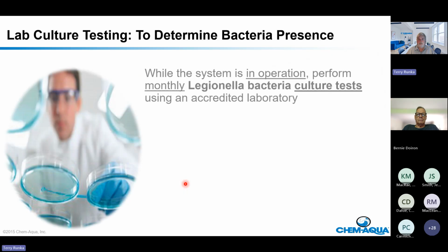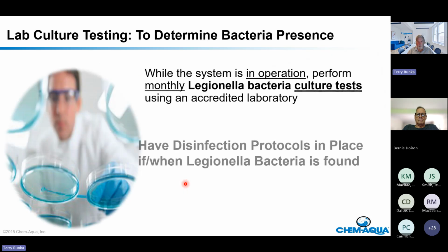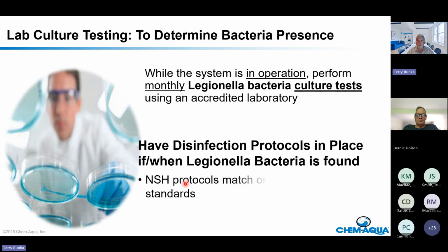Now, Legionella testing, on the other hand: if you want to know how much Legionella bacteria is in your water, then you have to specifically test for Legionella bacteria. The culture testing, which takes 7 to 10 days to get your results, is still the gold standard. qPCR is faster, but it measures both live and dead bacteria.